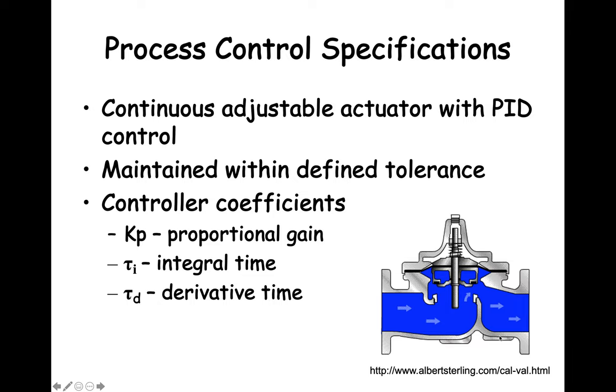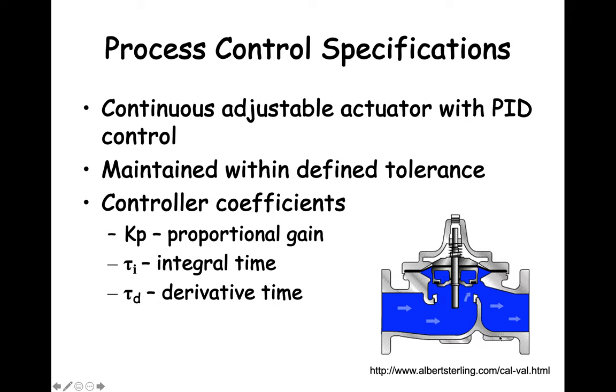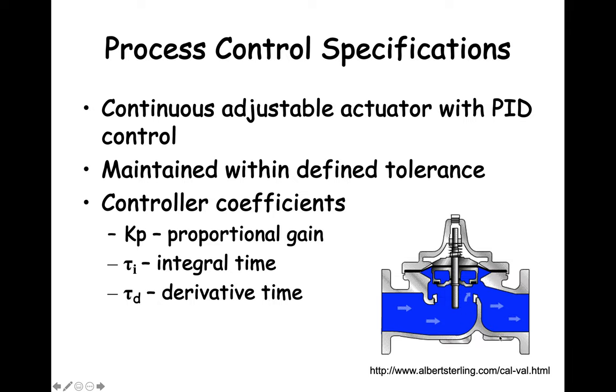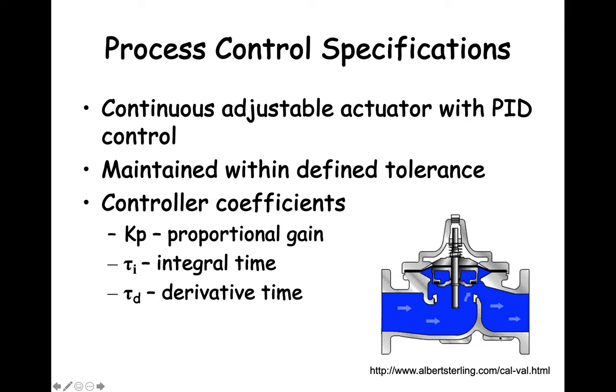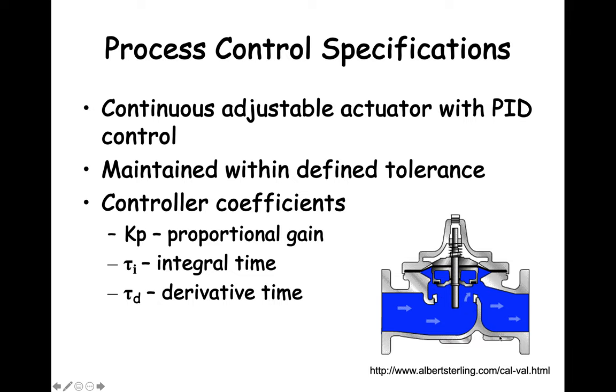To be able to use PID control, the actuator needs to be continuously adjustable. For example, the adjustable diaphragm flow valve shown in this slide could be continuously adjustable. However, a two-position solenoid valve cannot be used as a flow controller. Relays turn motors on and off. You could need a variable frequency drive actuator to provide the continuously adjustable motor speed you might want.